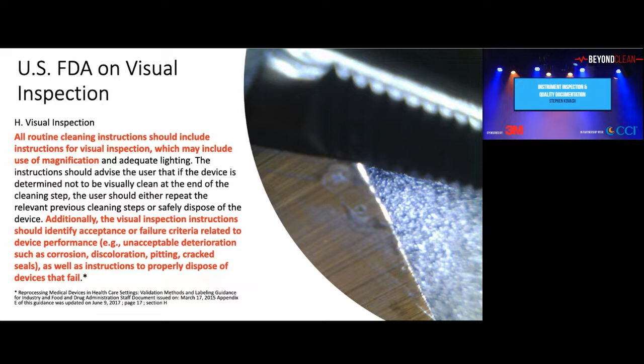Standards that support visual inspection. Here in the U.S., Standard 79: instruments should be carefully inspected for flaws, damage, debris, and so on. Verification of the cleaning process: they talk about protein as a marker commonly used to evaluate cleaning efficacy. They supplement when maybe the IFU doesn't give you a lot of information. You have to use your critical thinking skills. Support for magnification could be a flexible inspection scope or a borescope.